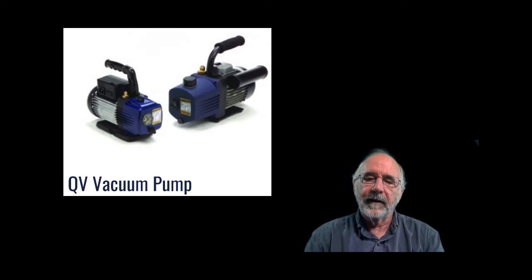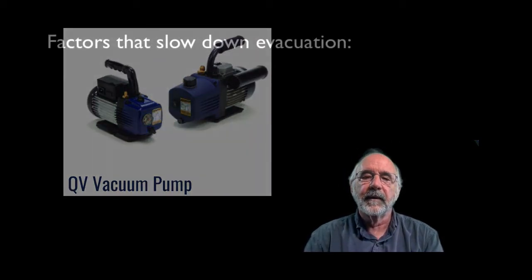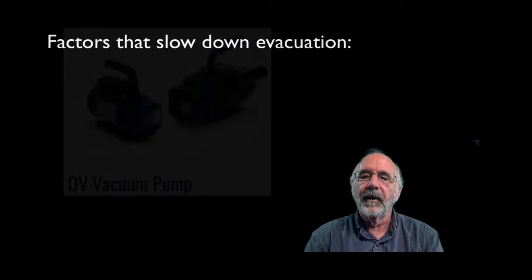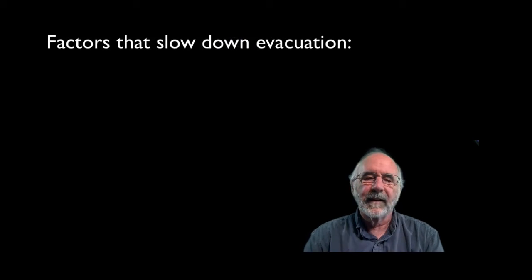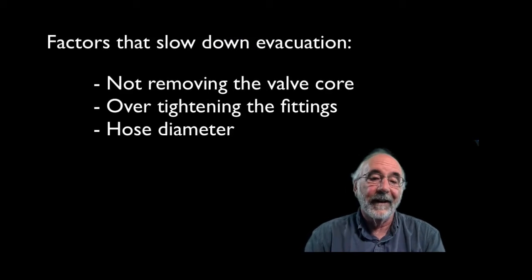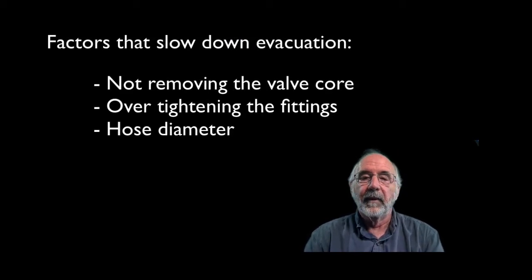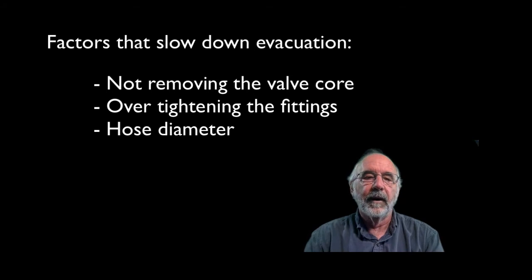A couple of other factors have a huge impact on restricting the flow rate: things like not removing the Schrader core, over-tightening the fittings, and another big one, the diameter of the hose.